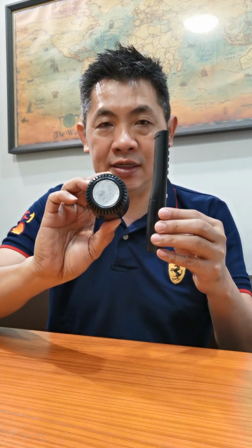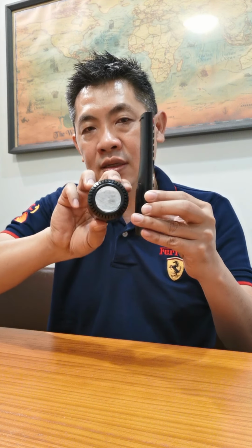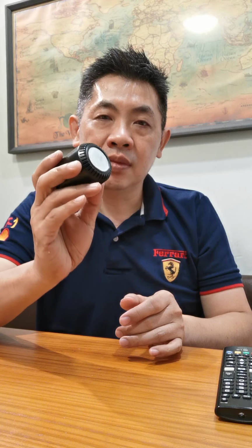So the fan coil, okay, imagine this is the fan coil. If I have a fan and I blow, after the coil I get cold air. But this is not the case. This is a fan. Okay, it turns and it sucks the cold air in, and then blows it out this way. So this material, the fan rotor, is always in contact with cold air. So despite the selection of material always being plastic, it can become so cold and begins to condense too.